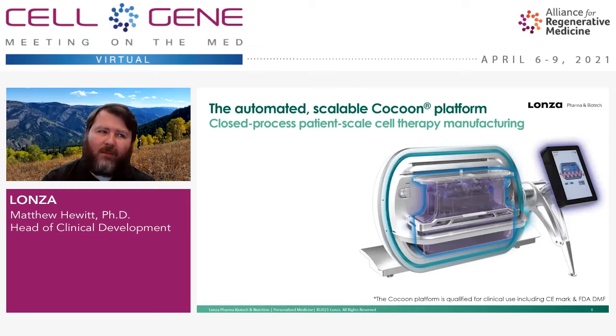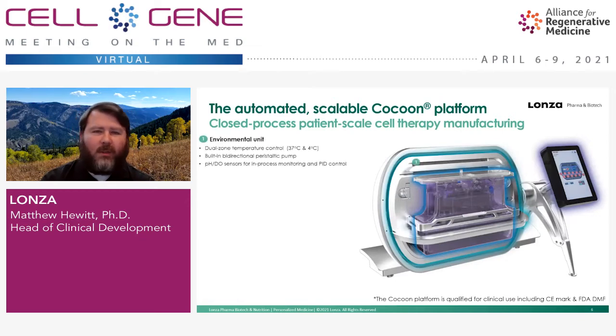The Cocoon is comprised of three primary components. The first is the environmental unit — the white pod you see in pictures of the Cocoon. Within the pod, we have a dual-zone temperature control system: the top zone is kept at 37°C as the culture zone for cells and active reagents, and the bottom zone is at 4°C for reagents, consumables, and waste. There's a built-in bidirectional peristaltic pump, actuators to open and close specific fluidic pathways, and pH/DO sensors providing real-time monitoring and PID control for pH and dissolved oxygen.